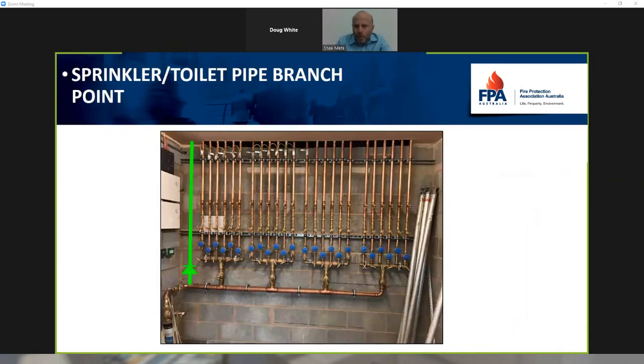This is what a water meter room might look like on a larger building, and there's some 20 or 25 water meters there, but you can see on the left-hand side I've indicated where a feed would tap in and feed all of the sprinklers on that floor, just that one floor. So the water meter cupboard on every floor would look like this. There'd be an individual tapping, the green one there, with the backflow prevention device, and it will be supplying all the sprinklers. The important thing to realise here is there is only one valve upstream of that. If you want to isolate the sprinkler system, you have to isolate that valve there in the bottom left-hand corner of the image, and that's going to shut off your sprinkler system, but importantly, it's going to shut off all of your drinking water at the same time.